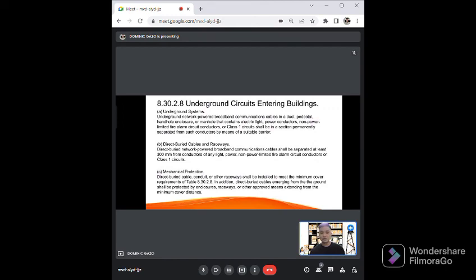For this underground circuits entering buildings, we are having underground systems. These cables in the pedestals, handhole enclosures, circuits shall be permanently separated from such conductors by means of a suitable barrier. For direct buried cables and raceways, these direct buried cables shall be separated at least 300 millimeters from conductors of any light and power.